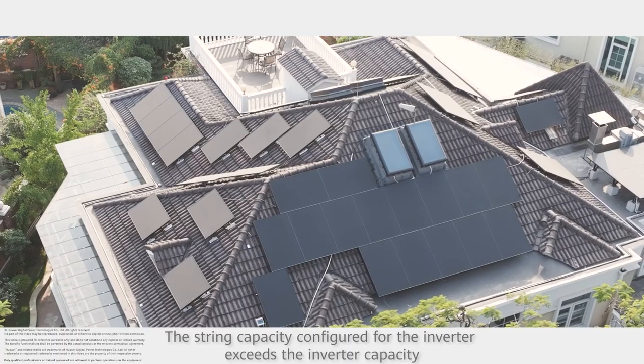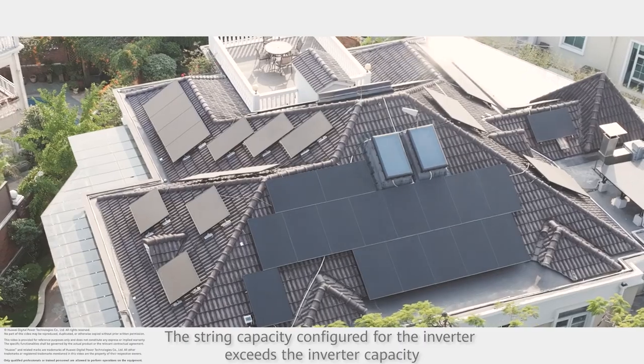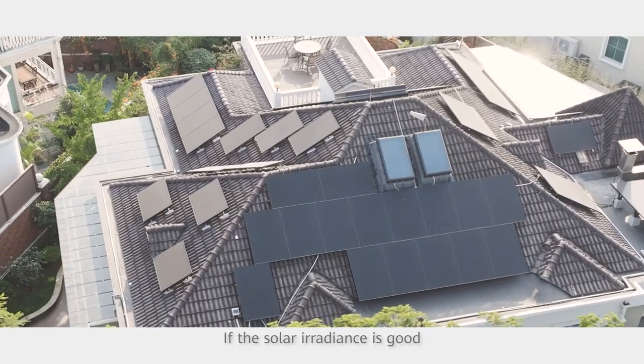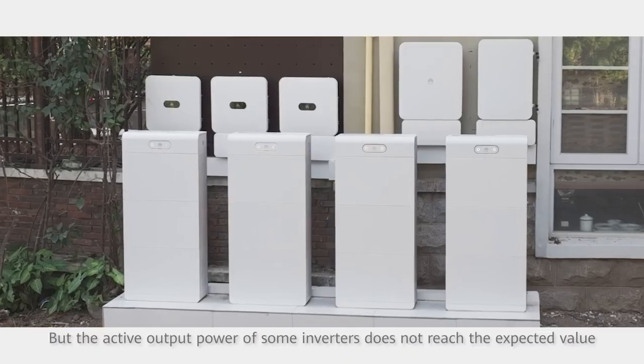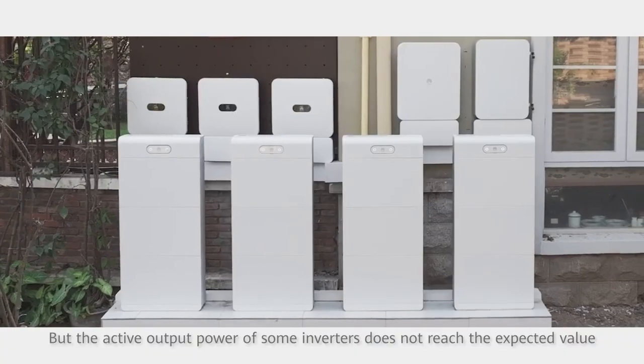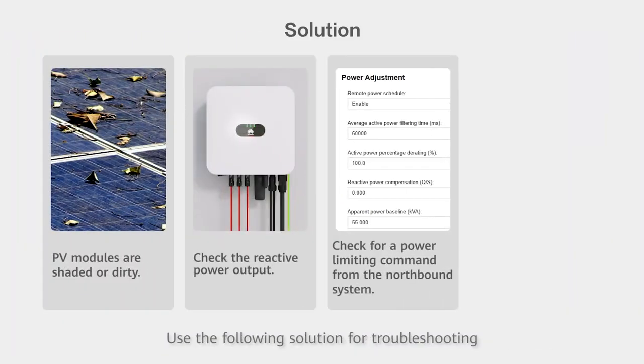The string capacity configured for the inverter exceeds the inverter capacity. If the solar irradiance is good, but the active output power of some inverters does not reach the expected value, use the following solution for troubleshooting.